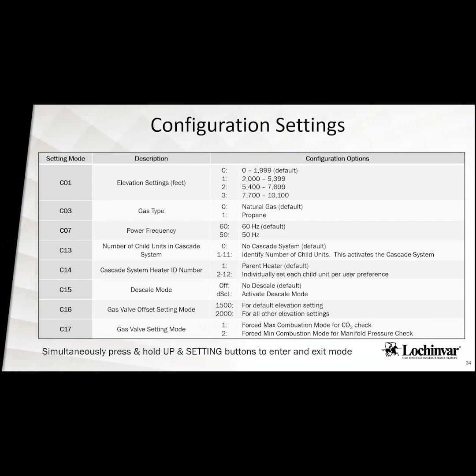So then, setting this unit up for elevation. We can go to 10,100 feet, and this will pop up as soon as you plug in the tankless unit. It'll walk you through this. So by default, it's going to come set from 0 to 2,000 feet. You would set your elevation from there.